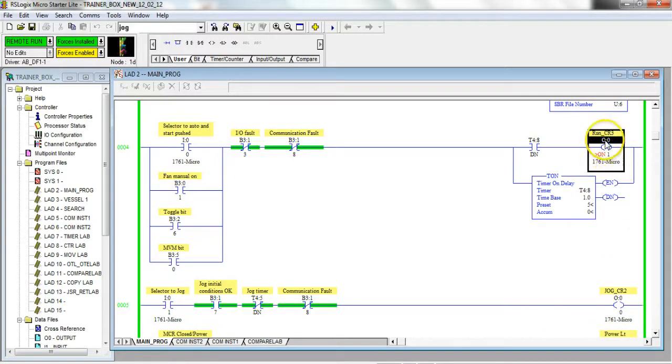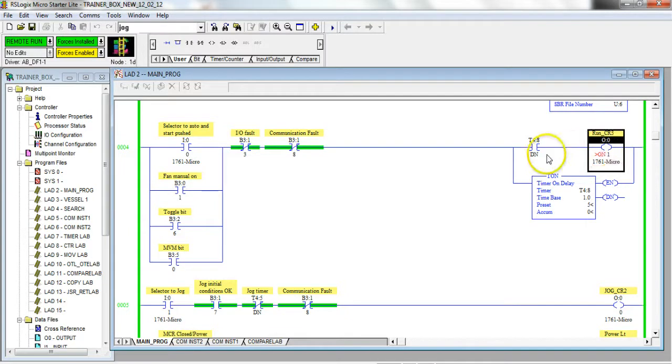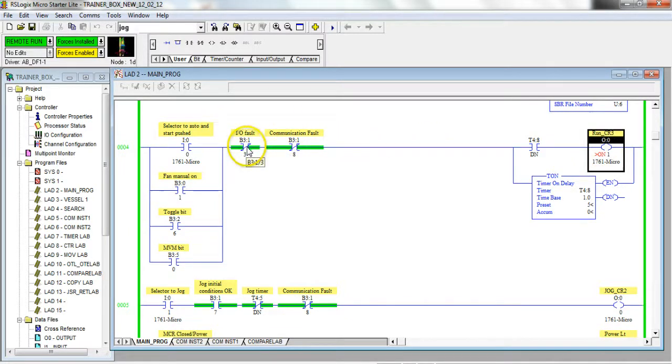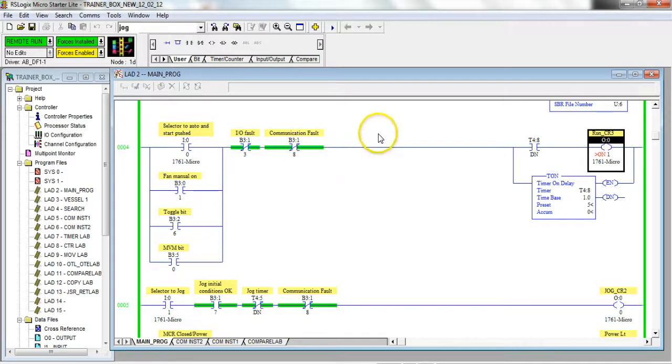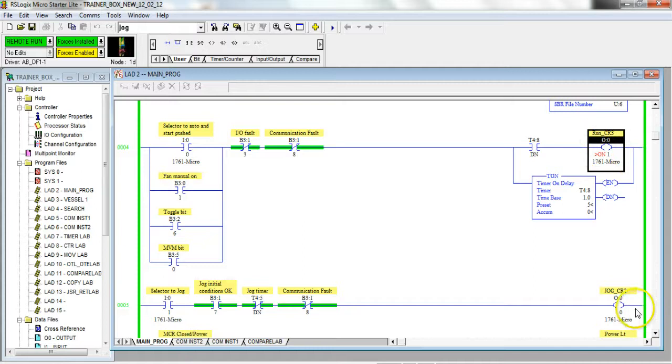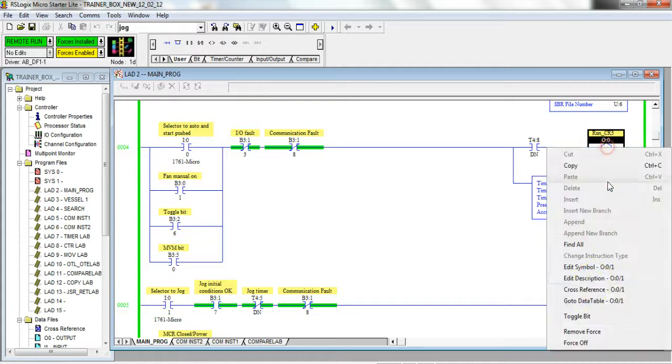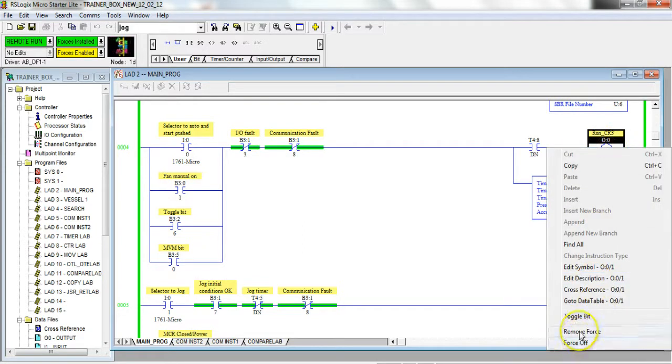The very important thing to remember about forcing anything is if you look at the conditions up to it, here I have some IO fault conditions and a communication fault. Well, if those faults were active right now, so if I had some communication fault somewhere in the plant, this thing's starting no matter what.